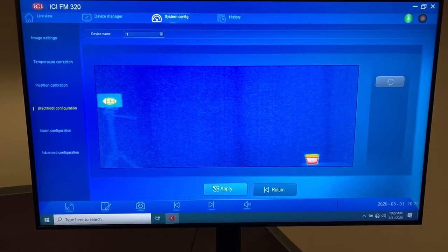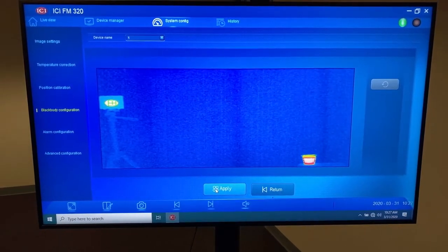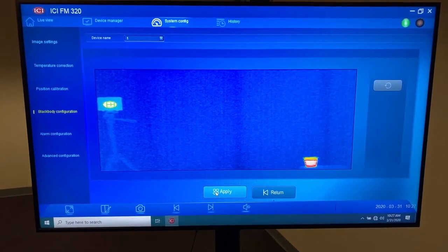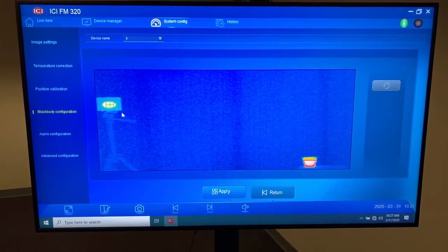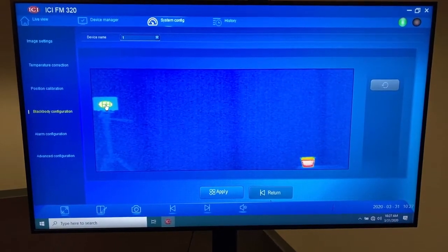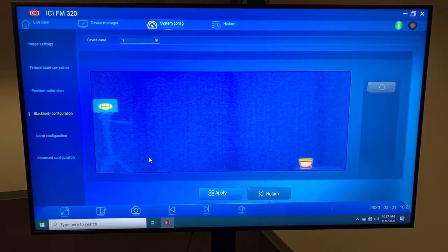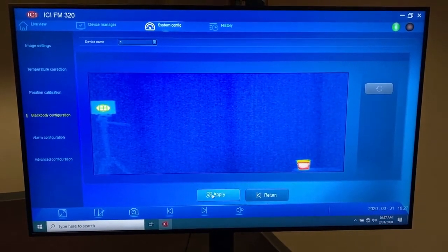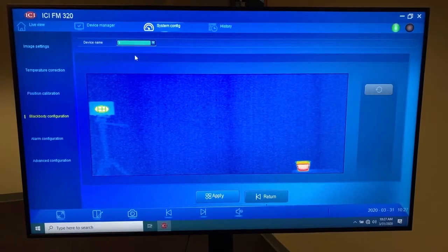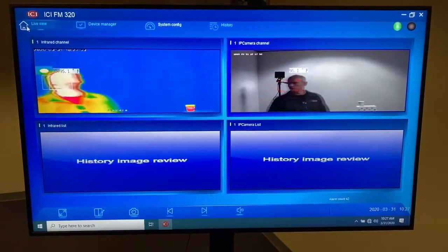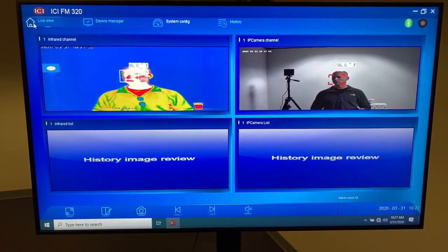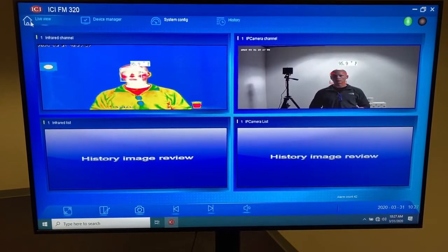The other thing that you can do in the event that you're getting some erroneous measurements, if you just adjust that crosshair a little bit, if you're getting some strange measurements, just reposition the crosshair a little bit. Sometimes it's a pixelation issue, and just reapply that setting, and then you should get temperatures that come right back into the norm. And I will step in front of the camera and demonstrate that again. So now we're right back into my normal state, my normal temperature.